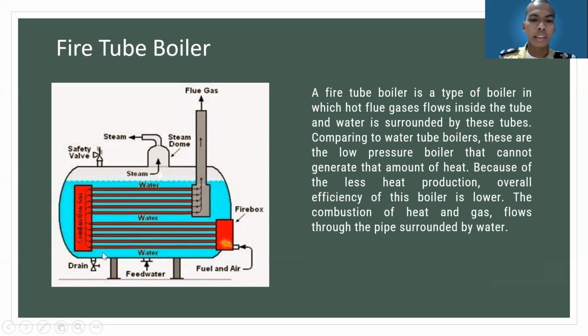We know that fire tube boilers come in all designs, and these types of boilers were famous in the 19th century, particularly appropriate for train engines. The combustion heat and gas flow through the pipes surrounded by the water. Most of the time, these boilers are considered for pressures up to a maximum of 250 psi and around 750 horsepower. The measurement of these boilers is done by their external diameter.